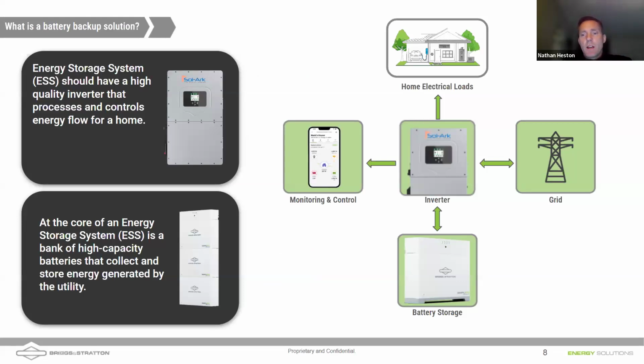The newer systems, let's level set. The newer systems based on batteries could operate in a very similar way, in which the inverter at the heart of the ESS system would essentially be like that transfer switch. When grid is present, power can come from the grid, flow through the inverter, charge the battery up if the battery's been drained, and then flow through the inverter to also power the home's electrical loads. In a grid down event, that power could then flow out of the batteries and cover the home's electrical loads until that grid comes back up or until the battery runs low.